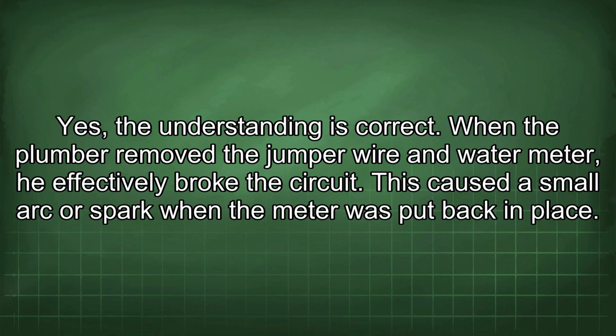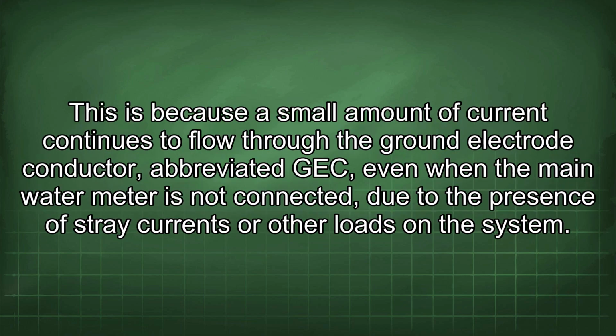Yes, the understanding is correct. When the plumber removed the jumper wire and water meter, he effectively broke the circuit. This caused a small arc or spark when the meter was put back in place. This is because a small amount of current continues to flow through the ground electrode conductor, abbreviated GEC, even when the main water meter is not connected, due to the presence of stray currents or other loads in the system.